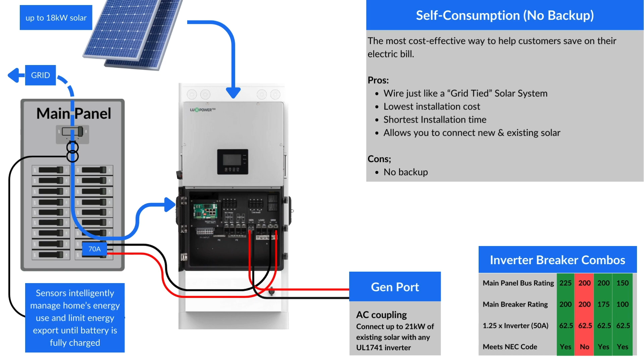Second, this installation is the same as grid-tied no battery installs of net metering 1 and net metering 2. It's simple to engineer and permit, and it has the lowest installation cost and shortest installation time. Plus, you get the added benefit of connecting existing grid-tied solar systems. You can choose a convenient location outside to install PowerStation Pro and then run a single 3/4 inch conduit line with 6 or 8 gauge wires from the conduit box to the main panel.